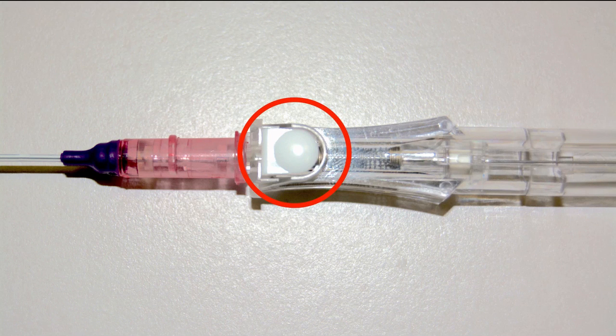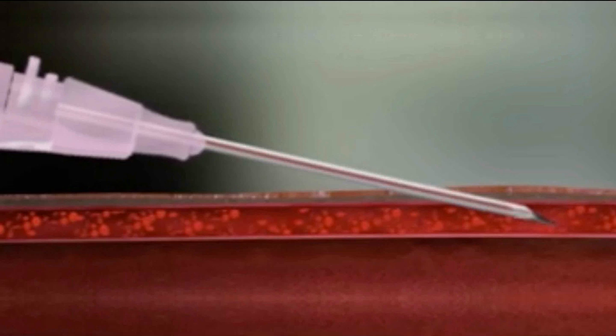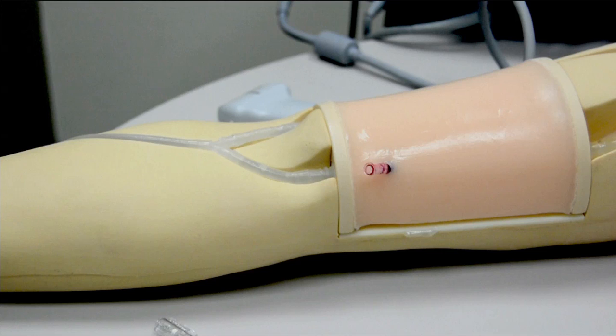This is the actuation button here. When you press that button, the spring will retract the needle and the wire is slightly withdrawn. There's still wire within the catheter itself. Once the catheter is in place, there will be blood flow in the catheter but not at the needle hub. So when you look at the catheter in place after retracting your wire, you will not see blood flow — that's because of that seal that prevented blood in the hub. So there's no blood splatter with the spring retraction of the needle, and it also allows you working time so you don't have excessive bleeding. The catheter is in place but not back bleeding — that does not mean the catheter is malfunctioning; that is a safety feature of the catheter itself.